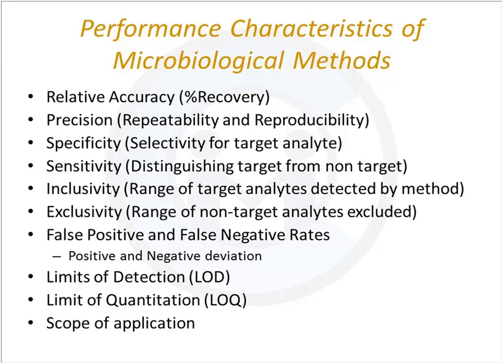We also have false positive and false negative rates, which are primarily applicable to qualitative methods. Now we're seeing the term not so much 'false positive/false negative' but rather 'positive and negative deviation.' The reason for this is that when comparing to a reference method — which in microbiology is traditionally a cultural method — many of the new methods coming along are PCR-based or genetic-based.